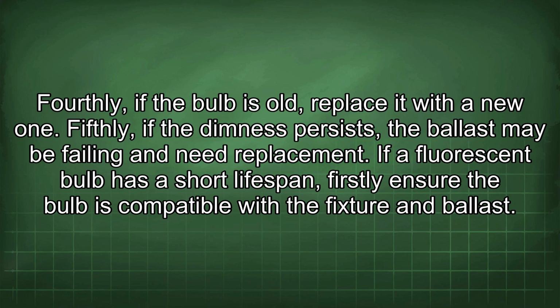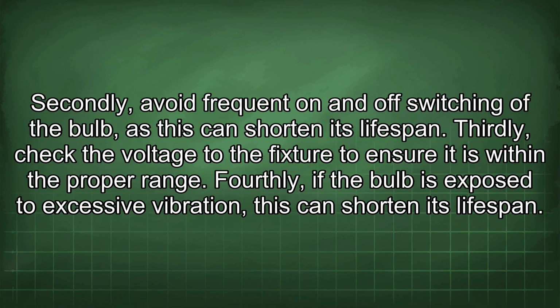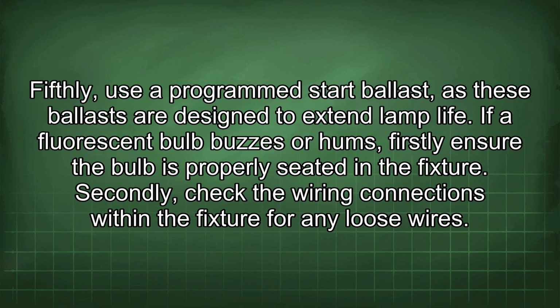If a fluorescent bulb has a short lifespan, firstly ensure the bulb is compatible with the fixture and ballast. Secondly, avoid frequent on and off switching of the bulb, as this can shorten its lifespan. Thirdly, check the voltage to the fixture to ensure it is within the proper range. Fourthly, if the bulb is exposed to excessive vibration, this can shorten its lifespan. Fifthly, use a programmed start ballast, as these ballasts are designed to extend lamp life.